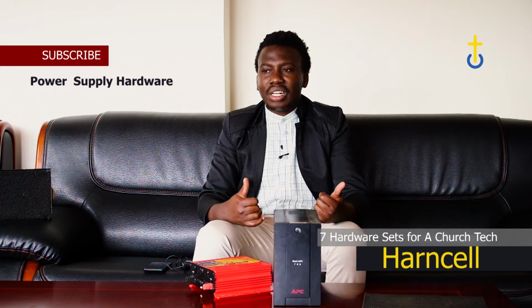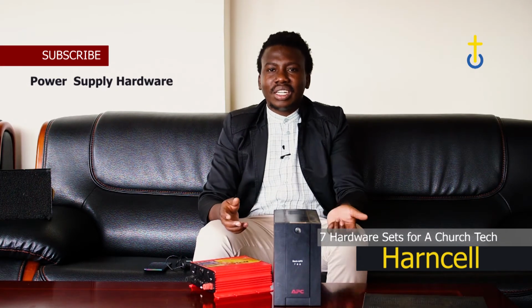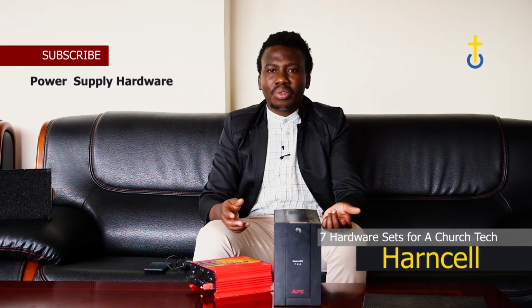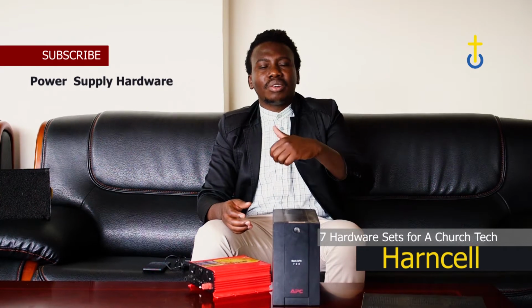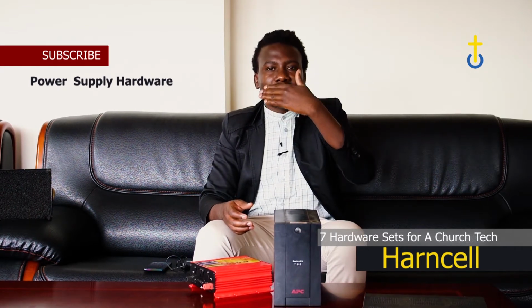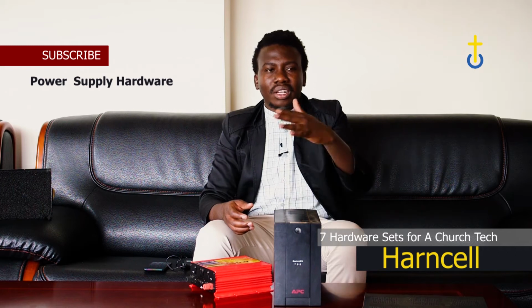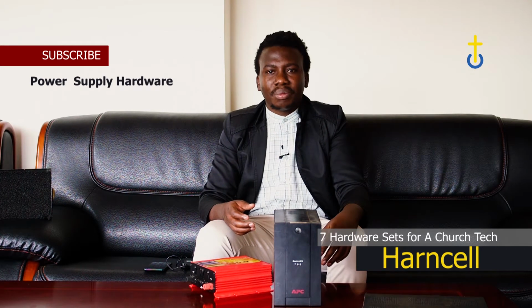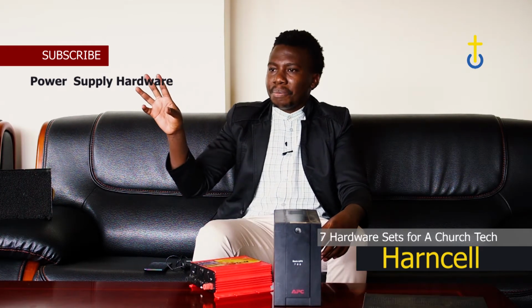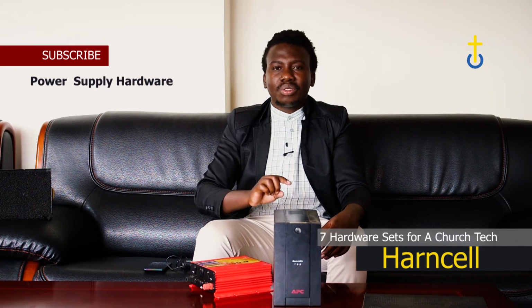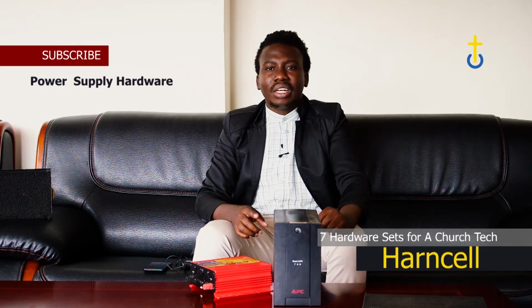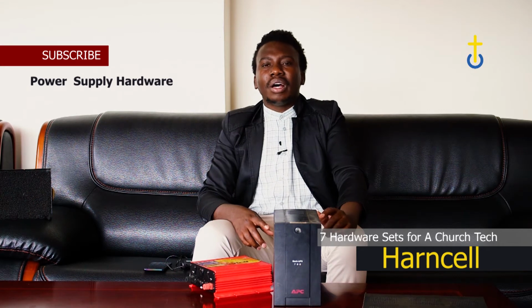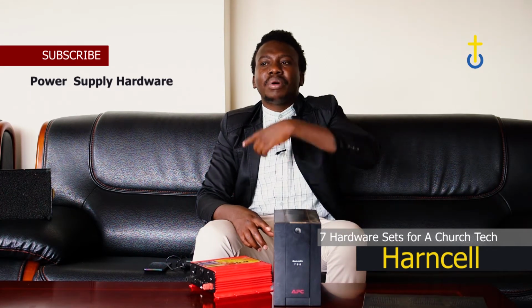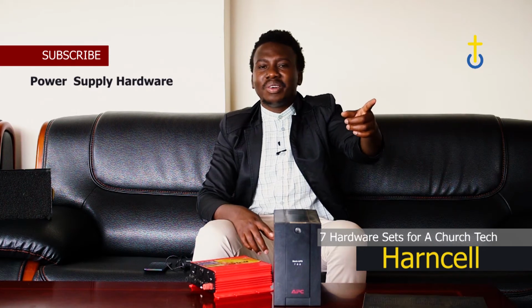And not just that. If you're running a generator at your premises, and let's say you've been having interruption on the other side from the power supply company, when you power on your generator without cutting out the supply on the other side, you might end up supplying electricity back to the power poles.